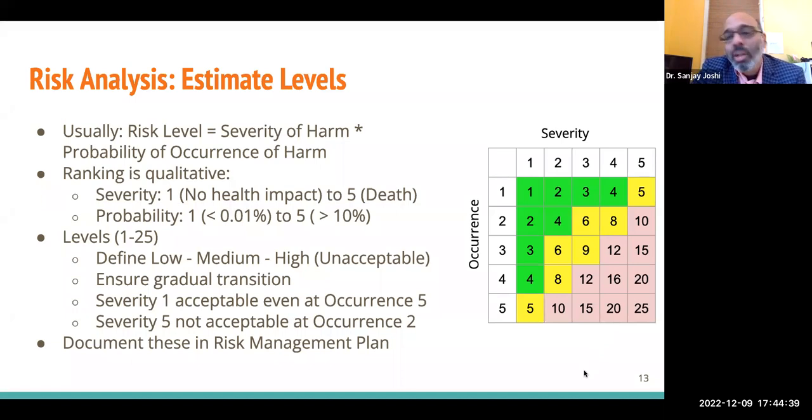Before you go to the government for approval for any studies, any clinical studies, any government obviously wants to protect its people. They are going to ask you, what are you going to do to my patients? And at that time, if you don't have your risk analysis, you will be in a tough spot to explain why even for clinical trials, this is safe. So doing risk analysis is going to be really, really helpful to get approvals from the government.